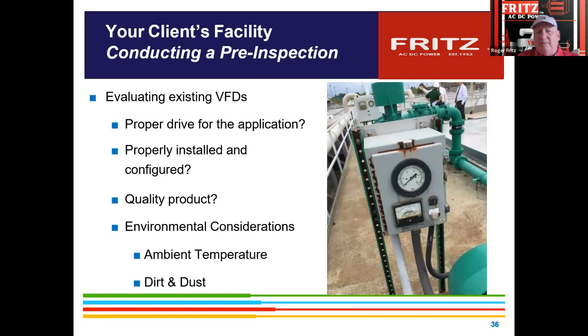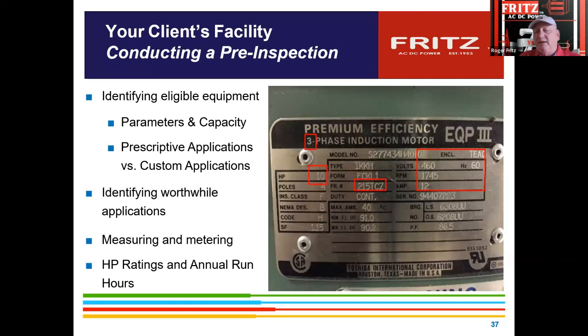Getting the compatibility correct to the motor is really key. We recommend people take pictures of the nameplates, so that a motor specialist can look at it and see what its design was and what its amperage loads are. Application errors have been made because a 900 RPM motor at 100 horsepower has a different amperage rating than the same motor at 1800 RPM. You can't turn an 1800 RPM motor down to 900 RPM and get the same torque out. So it's important to understand the torque factors, especially in more constant torque loads.